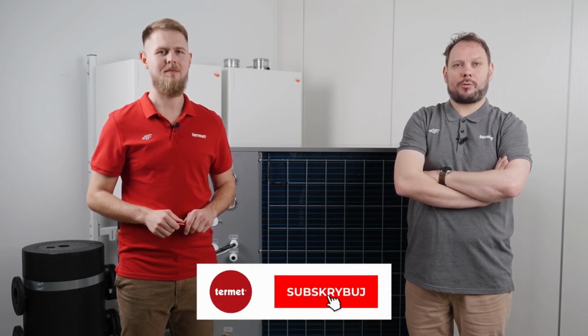Where might frost or ice on a heat pump come from? A heat pump, to effectively heat a house, gathers heat from the air. During warm weather, the condensate accumulating on the evaporator simply drains away. The situation changes in autumn when temperatures start to drop and the air becomes increasingly humid. The condensing vapor begins to freeze, forming a layer of frost or ice.